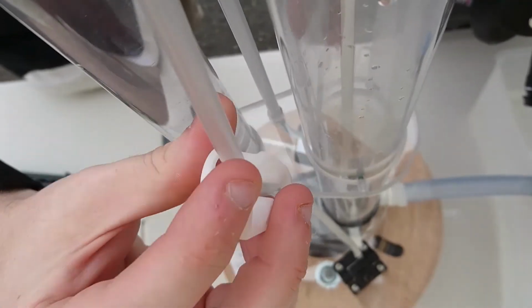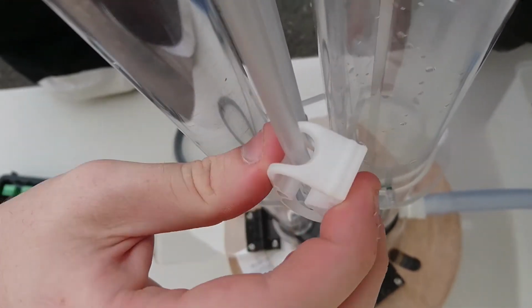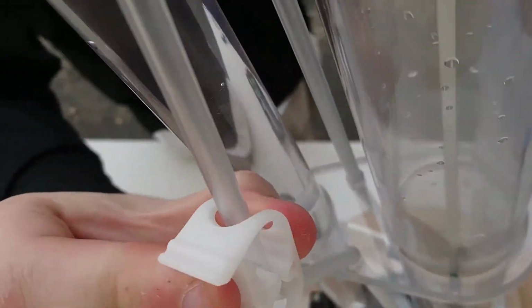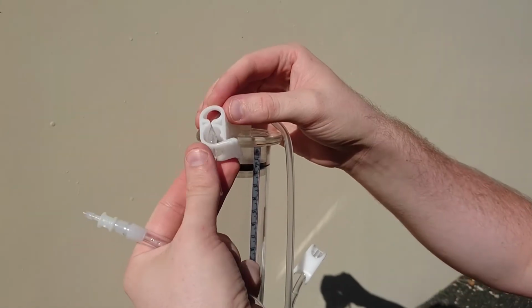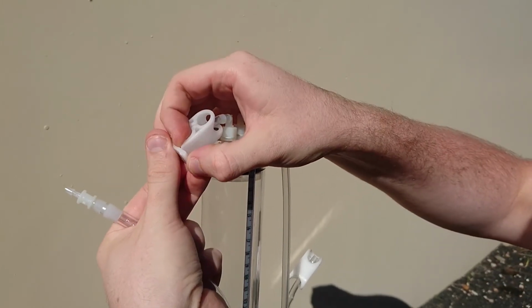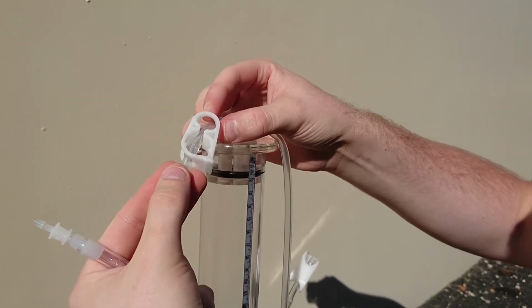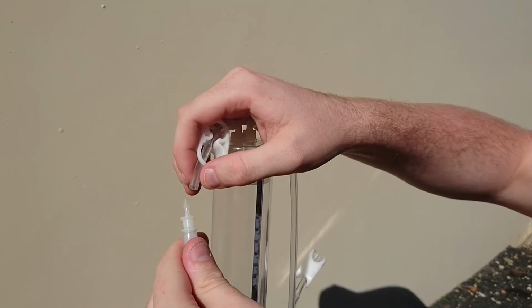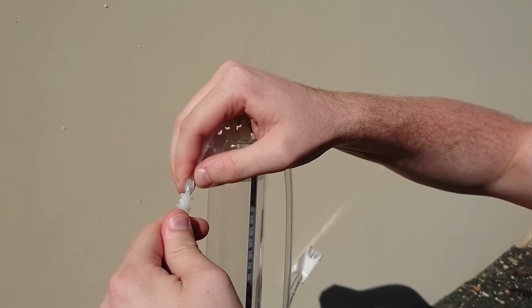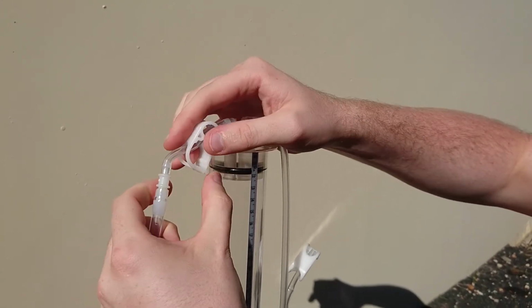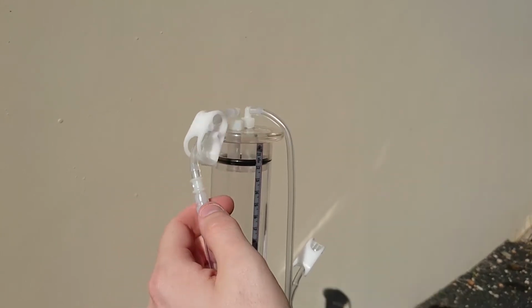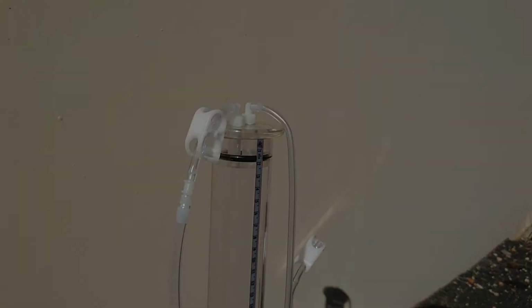Next, close the clip valve leading from the top hose of the bubble tower to the bottom hose of the water tower. This is to isolate them. Now open the clip valve on the top end cap's inlet tube to the water tower, then connect the supplied vacuum pump to this hose ready. Now the infiltrometer is ready to have water pulled up into the water tower section.